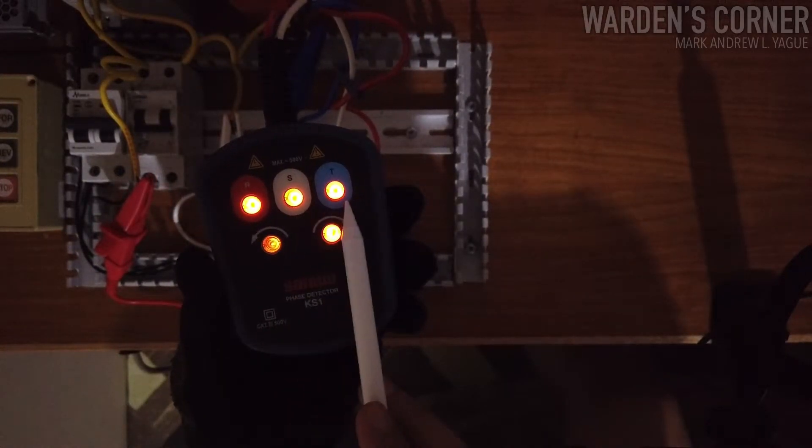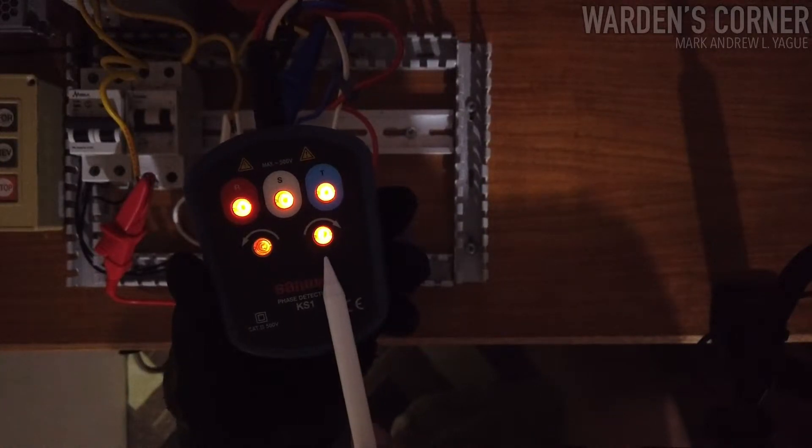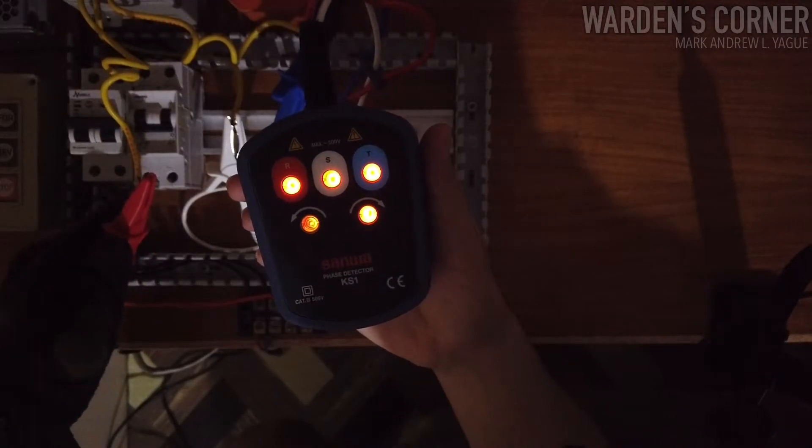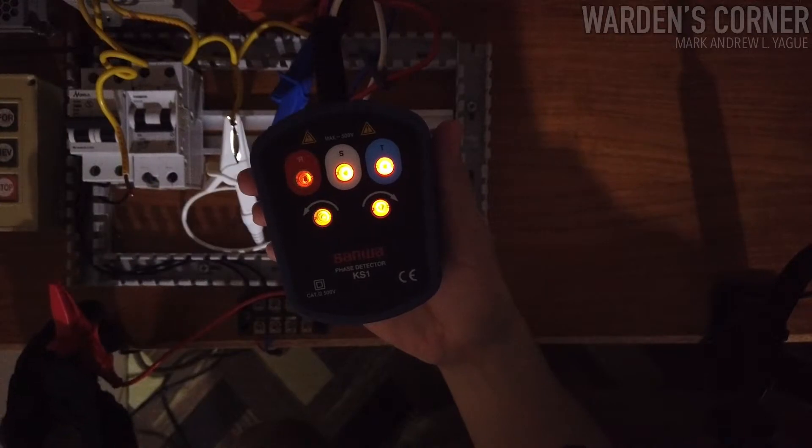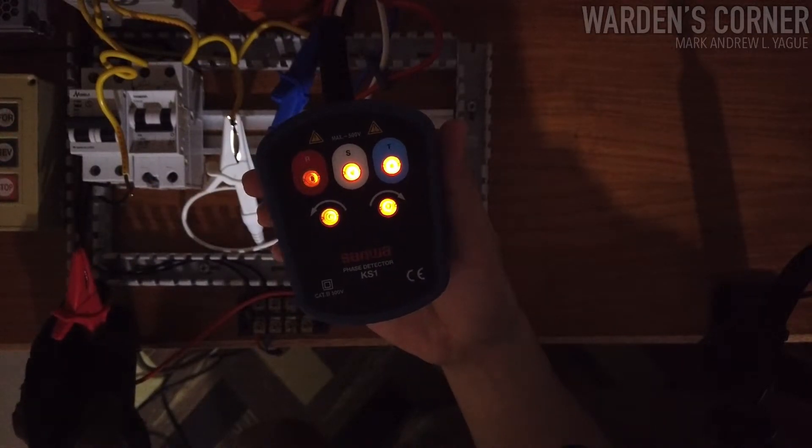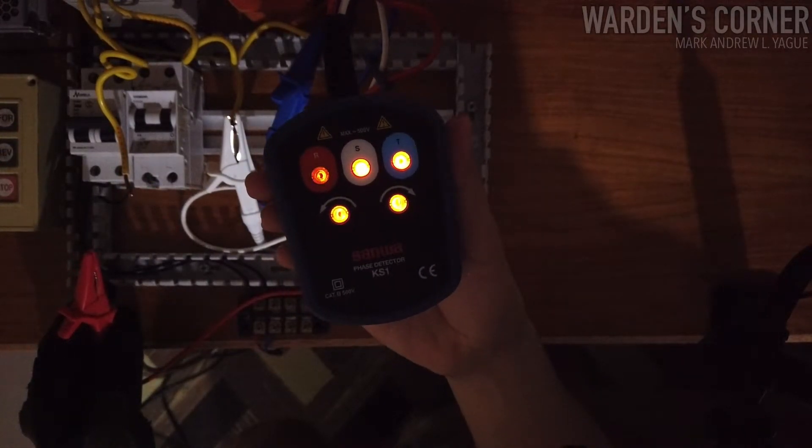When there is no open phase, indicators of RST are on. What if one of the phase is open? Its indicator R, S, or T is off, and both phase rotation indicators are on simultaneously.